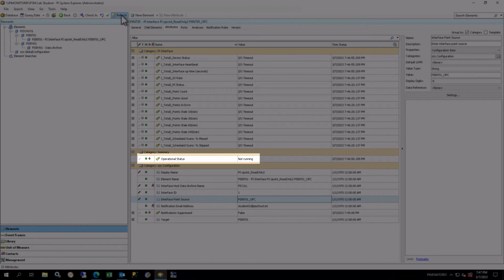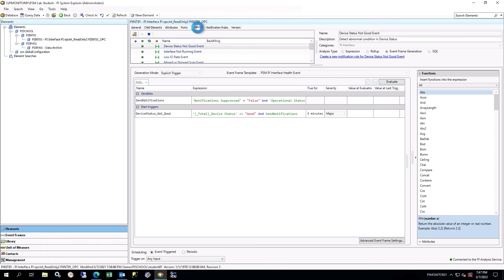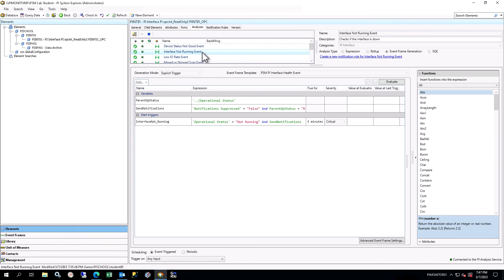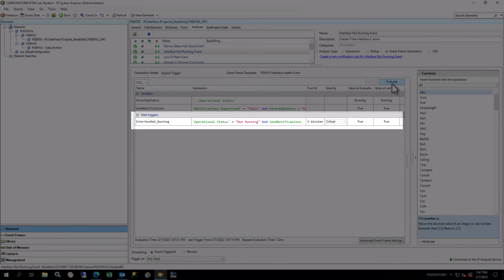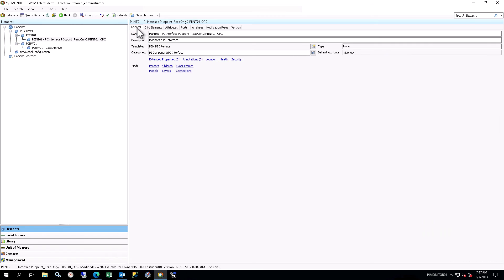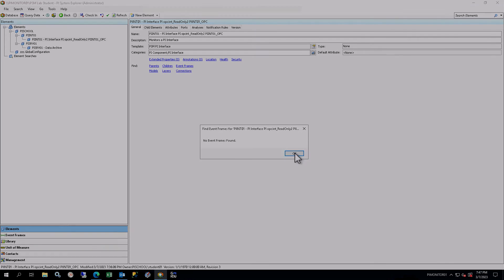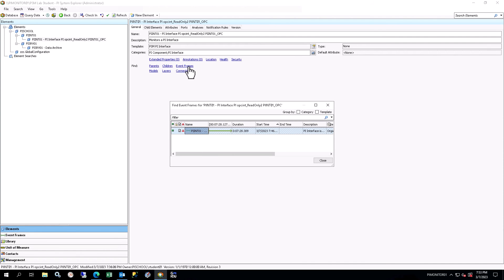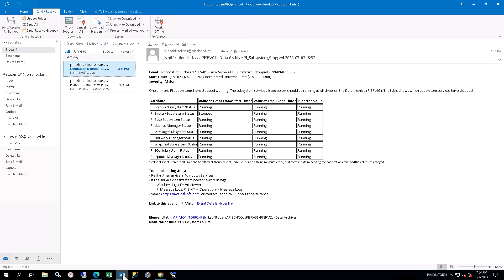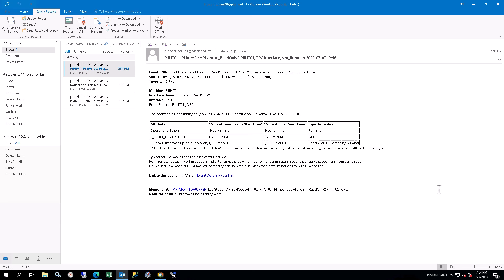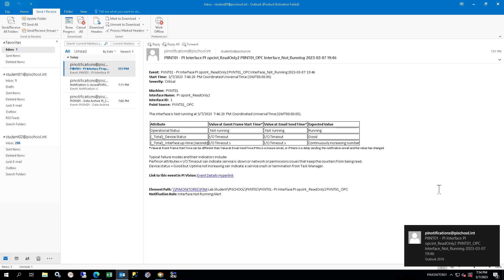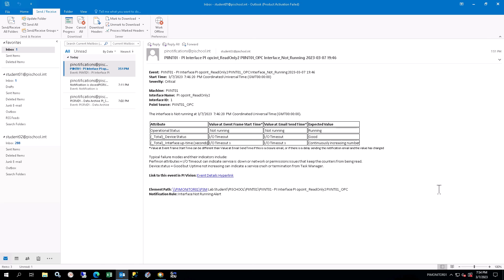Select the Analyses tab and select the Interface Not Running Event Frame Analysis. Click Evaluate, and see that the evaluation for the start trigger is true, indicating that there is an interface issue. Select the General tab and click on the Event Frames link. After the Event Trigger condition has been true for 5 minutes, you will see a new Event Frame for the Interface Not Running Event. The blank end times indicate that the Event Frame is still active. Close the Event Frame window. Open Microsoft Outlook on PI Monitor 01. In the Student 01 at Pischool.in inbox, locate the email for the Interface Not Running Event notification. Refresh if it is not showing up. Open the email and look at the content. The Event Name — which is also the email subject — indicates the name of the triggering condition: Interface Not Running. The table provides some key information on performance indicators. Below the table are instructions to troubleshoot the issue and a link to the Event Details view in PI Vision.